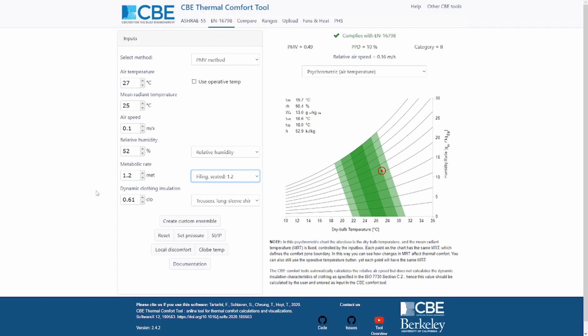On the right side we have the results. For this set of conditions, we can see that the PMV is 0.49 and the PPD — the Predicted Percentage of Dissatisfied — is 10%. In compliance with EN16798, we are also reporting the comfort category. This standard defines three comfort categories: category one, two, and three, and we report which category the conditions fall into.